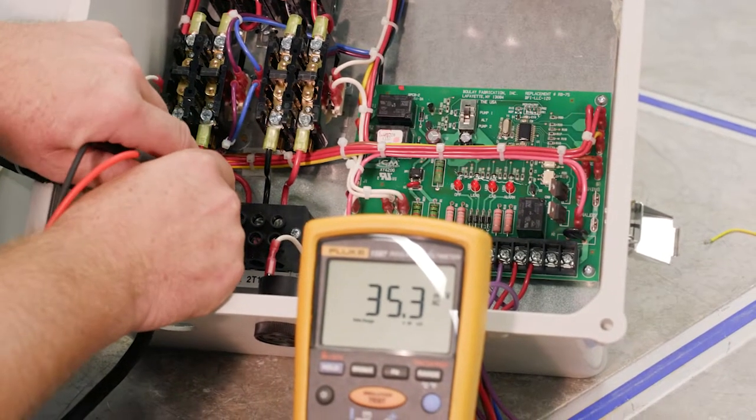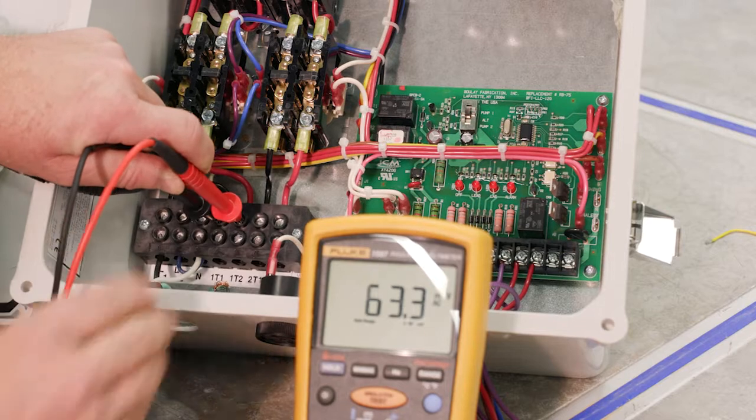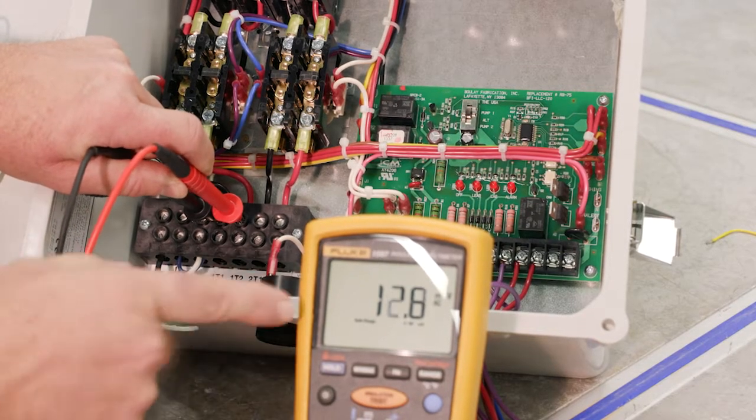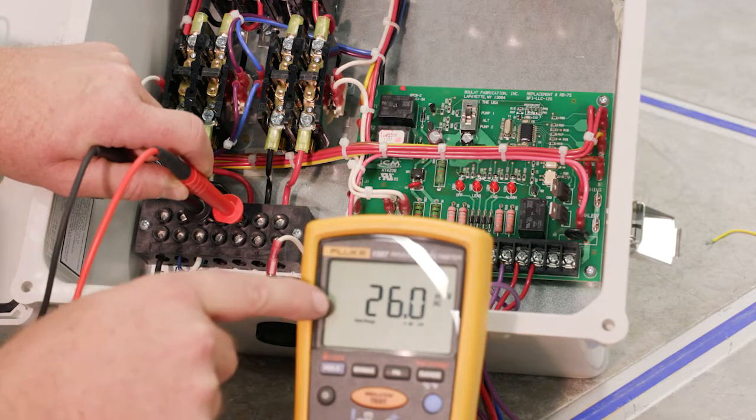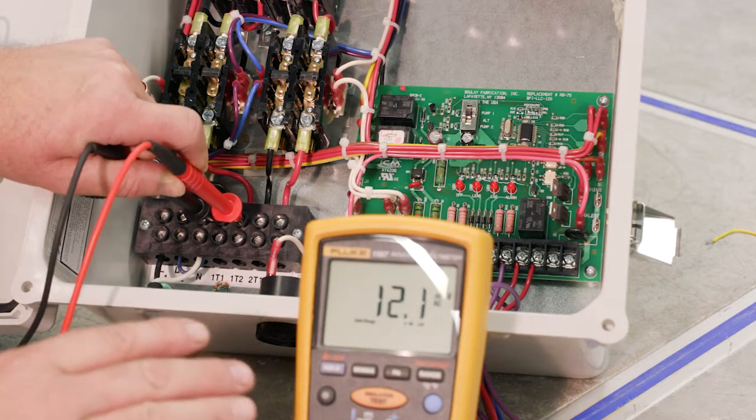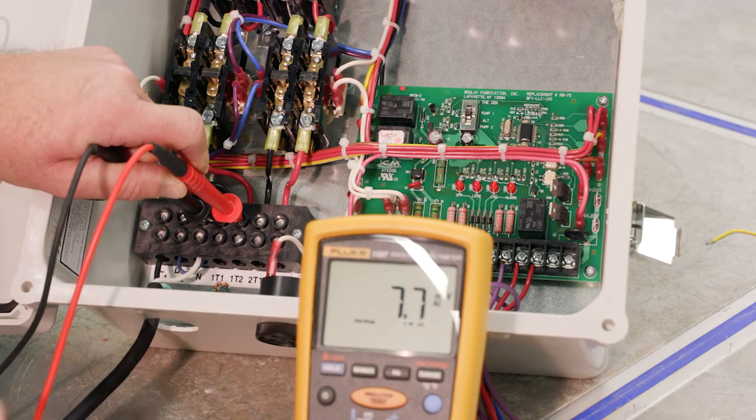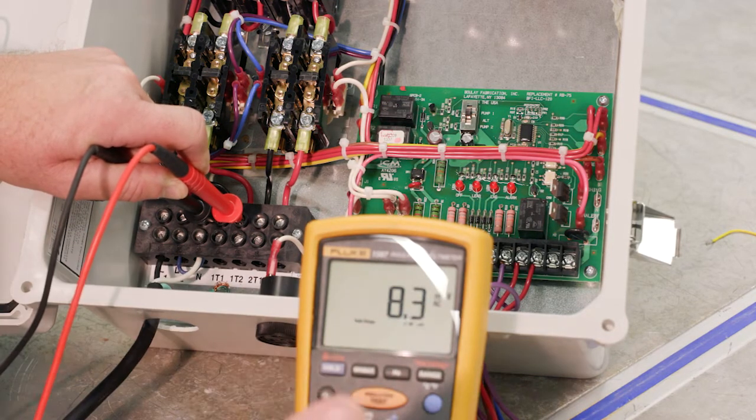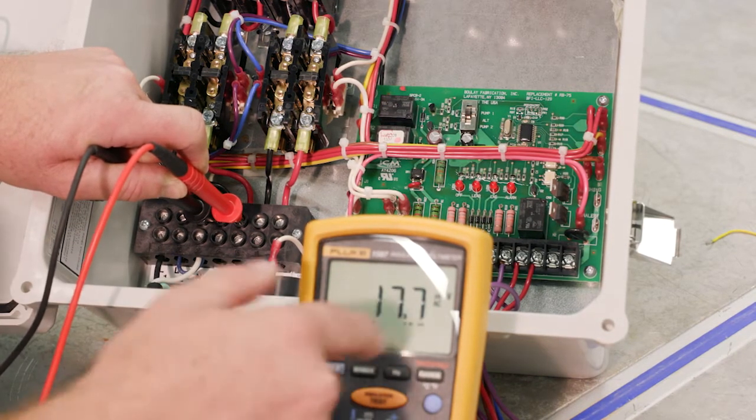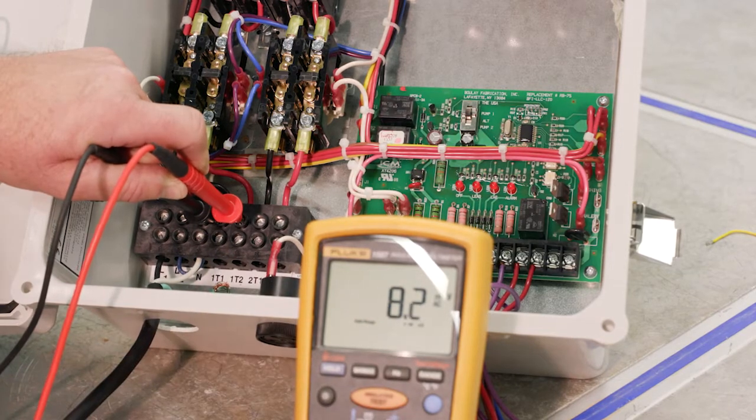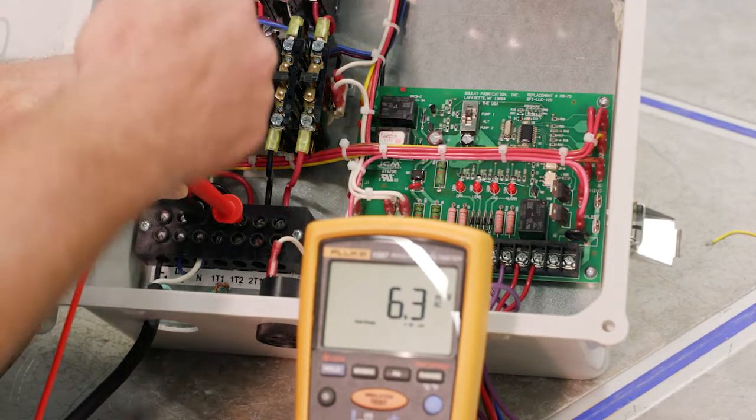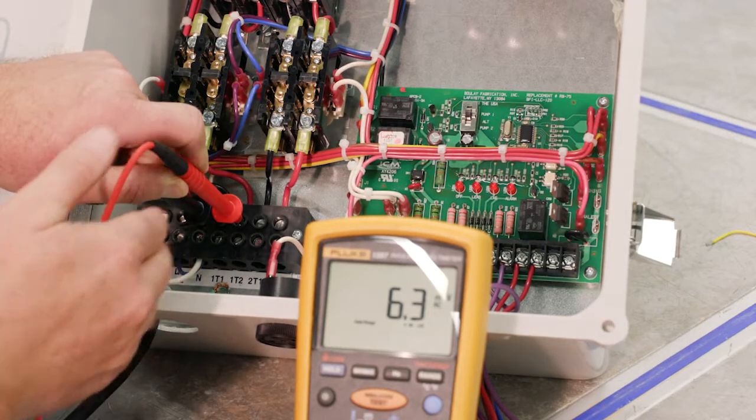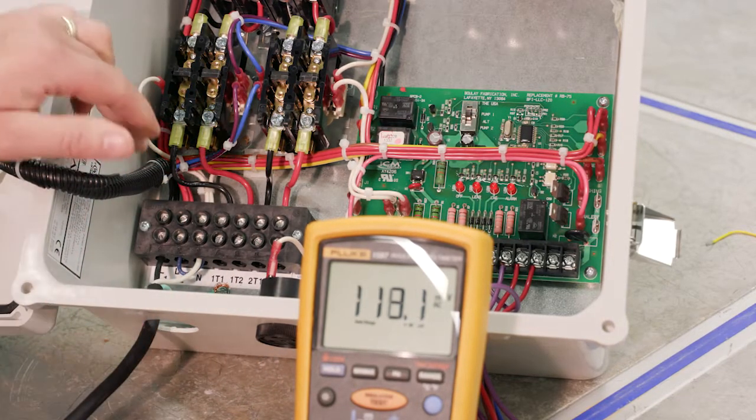And so here's one thing that is a little difficult sometimes with your digital meter. Here, we can see we don't have that lightning bolt. We really don't have any real power because that contact is open. It's showing something, but it's really now millivolt scale. But again, if that contact were closed, then that power should flow and we should see that same voltage to the pump itself.